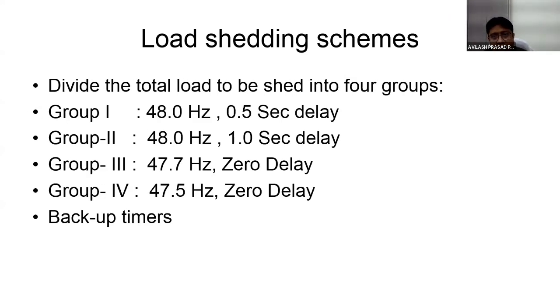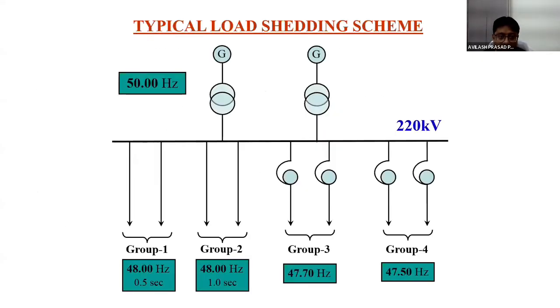We have divided the total load to be shed into four groups, that is 1, 2, 3 and 4. The load of group 1, in the range of 48 Hz with 0.5 second delay, will shed first. Then group 2, at 1 second delay for 47.7 Hz, with 0 delay in group 3, and 47.5 Hz with 0 delay in group 4. And there are backup timers.